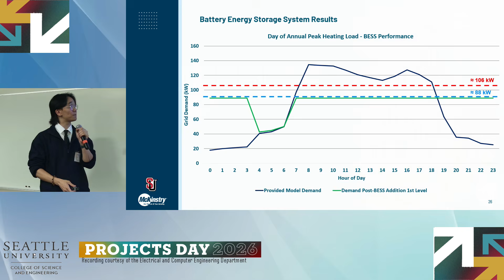When applied to that figure that we've been going back and forth with, just a reminder, here's that normal electricity use as well as the limit that we set for ourselves. For this specific day, our predictive control logic set an internal limit of around 88 kilowatts, and you can see that reflected in how the battery is charged and discharged. Early in the morning, the battery will charge up until at capacity, and then during periods where the building's electricity consumption goes above that limit that it's set for itself, the battery will discharge. Later on into the night, the battery begins charging again, recuperating all of that used electricity.